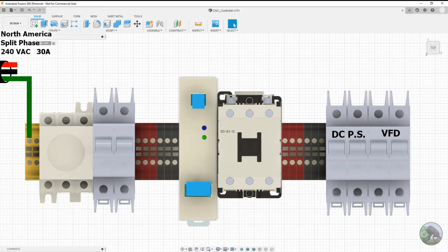It's a safety feature. The idea being that if you ever have a bad connection or other fault and mains power is somehow energizing the enclosure, that the current will find its way back to your panel through this ground wire rather than through your body or anything else in the shop. And so it's really important that this connection be good. And so it's, from a safety standpoint, it's probably the most important connection in the entire box. So next, the 2 hot wires go straight into the rotary disconnect. And when this rotary disconnect is open, this is as far as the power goes.